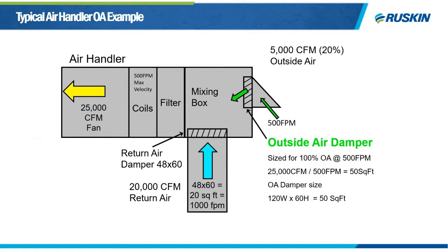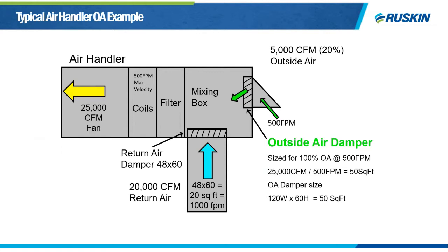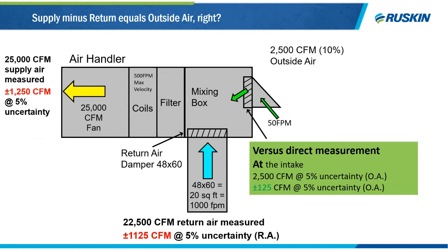Using a typical air handler as an example: outside air openings are sized large enough to prevent moisture carryover and provide 100% outside air. With a supply air rating of 500 feet per minute and a 25,000 CFM fan, we would end up with a 50 square foot outside air opening. One method for measuring outside air is using supply and return air, but the large volumes being measured almost guarantee inaccuracy. At a 5% inaccuracy with a 25,000 CFM fan and a 22,500 CFM return air, you end up with uncertainty almost as high as the air you're actually measuring.